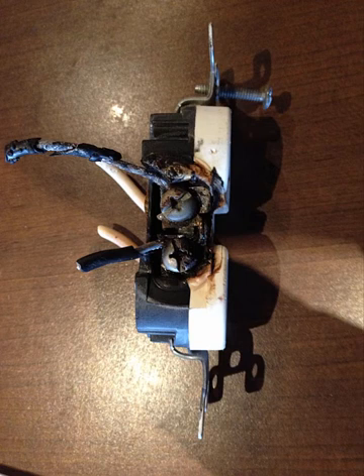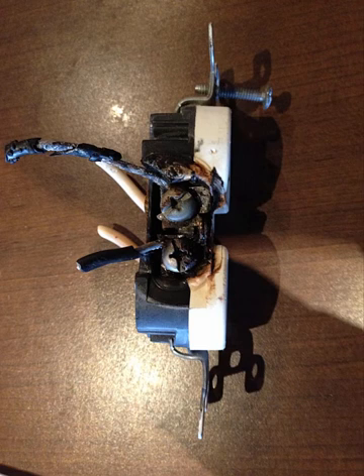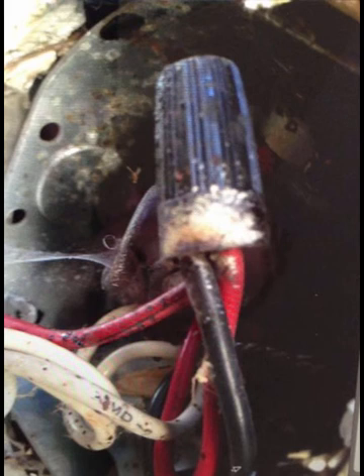Aluminum wiring has been causing a problem for a couple of decades now, and houses that are now 40-plus years old are having problems even more so. Aluminum wiring has what's been called creep, which is a response to different temperatures that occur as current passes through a connection — be it a light switch, a light, or any other electrical connection in the home. This creep causes aluminum to expand and contract much further and much faster than copper does, creating gaps within the connection over time, which can cause arcing or sparking and enough heat to cause fires.